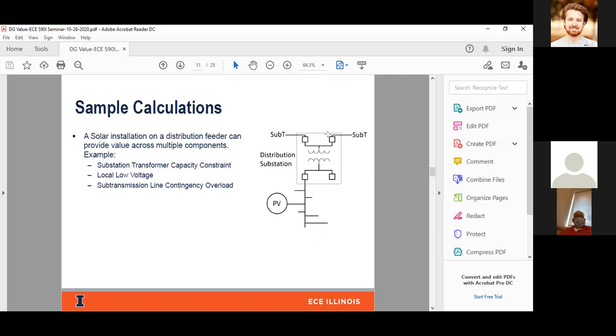So here's an example where it's a substation transformer fed by a subtransmission line. This is the higher voltage. Typically in Illinois, this is a 34 kV line or a 69 kV line, and then goes through transformation and turns into a distribution level circuit, typically 12 kV or 4 kV. That's where you see most of the distributed generation installed. A lot of the incentives in the state of Illinois are to keep the DG below 2 megawatts capacity, so a majority of them are installed on the distribution side of the system.